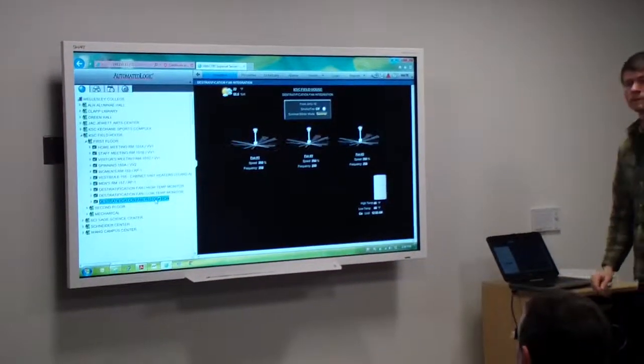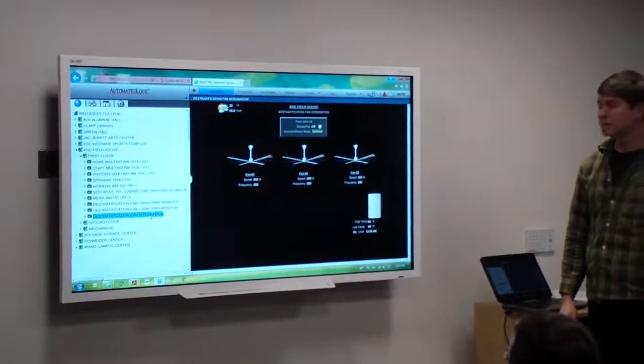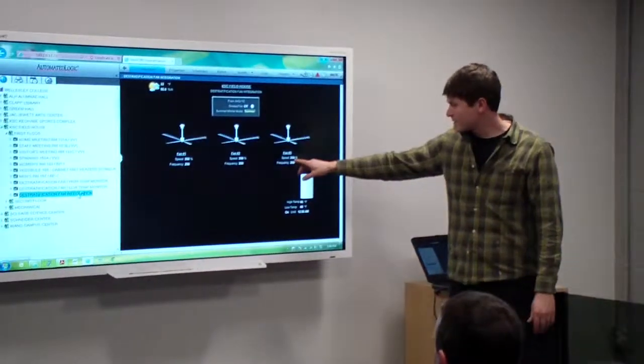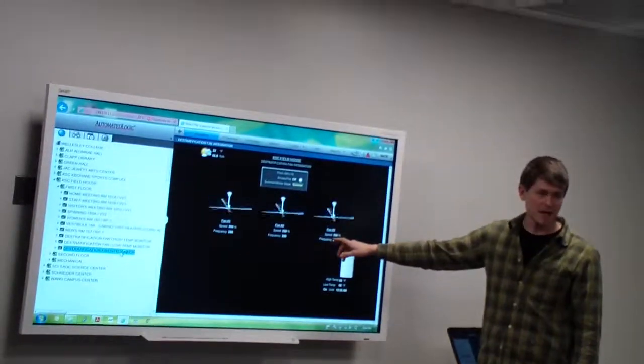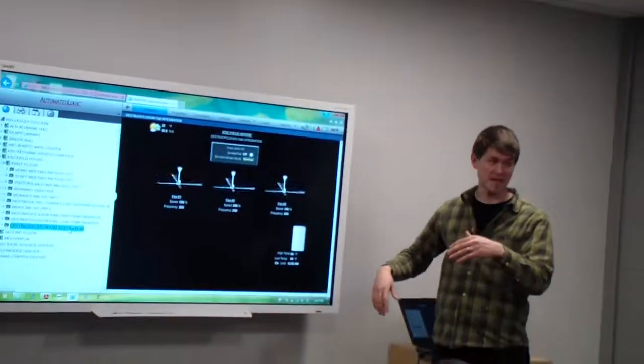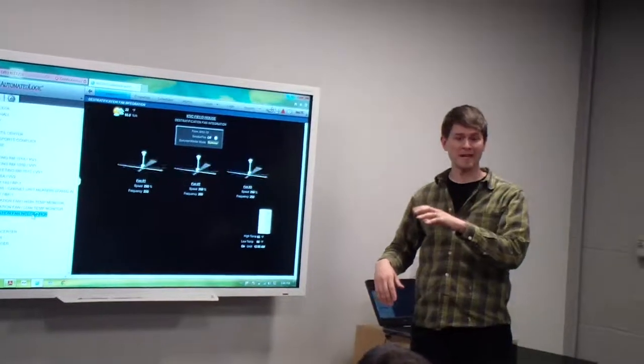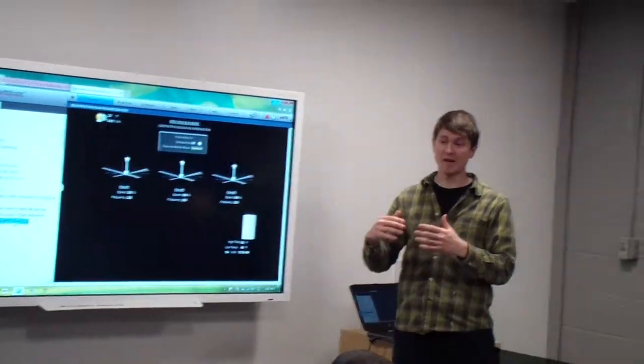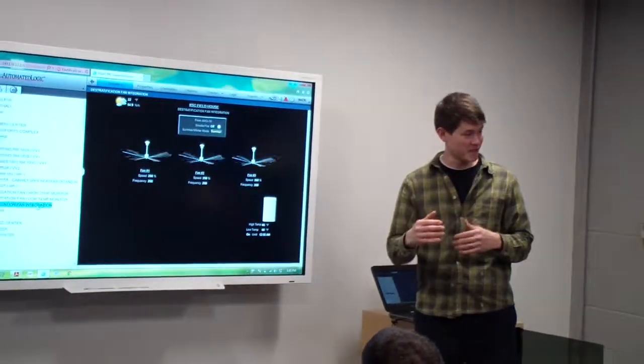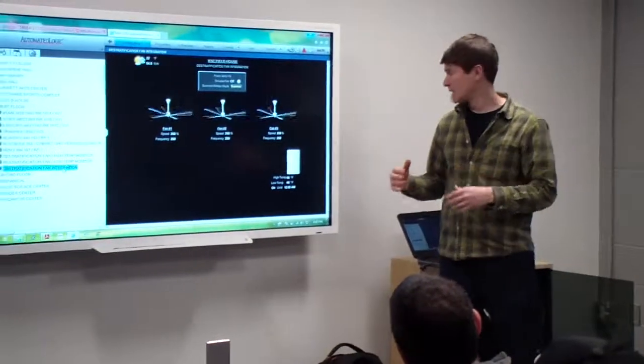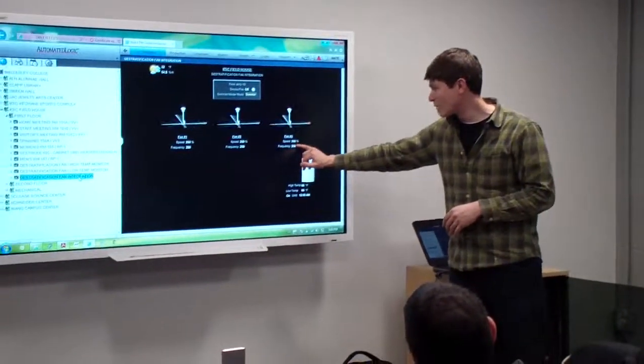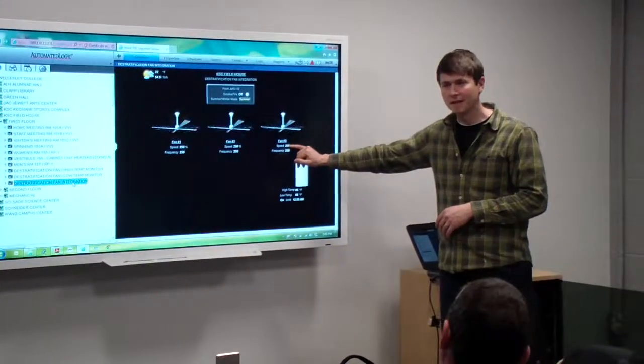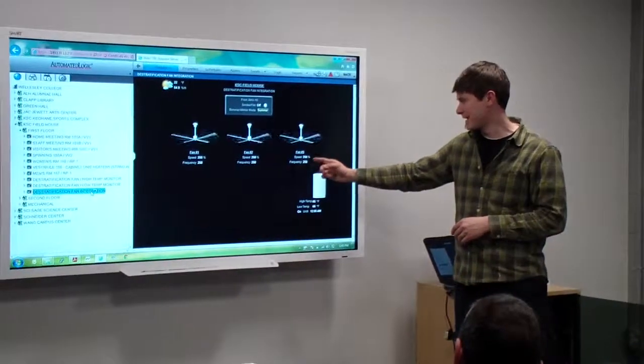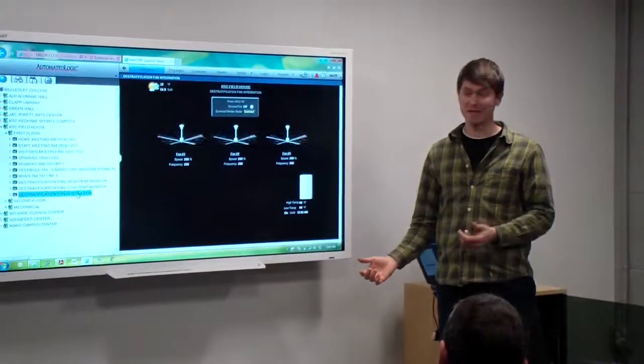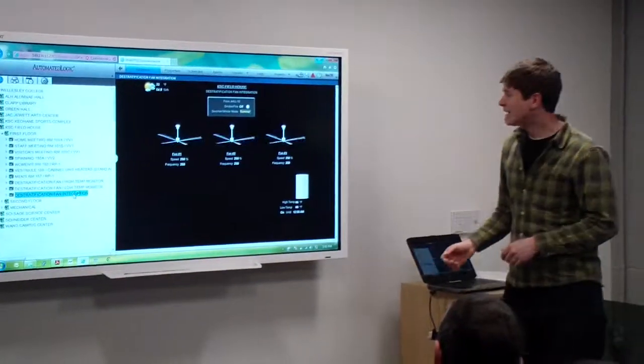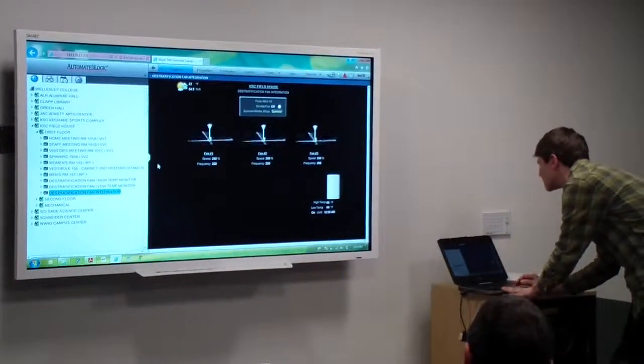Do Dennis and Billy have control of those fans or no? Yes, they do. Through integration, you'll notice that this number seems a little out of whack. The Yaskawa drives look for 100, or a 100 command to them is actually 10%, or 10 hertz to the drive, and a 600 command is 60 hertz to the drive. So I'm going to change the program, we'll do a little division so it'll depict more clearly what's there, because seeing it at 250, it's not spinning at 250% of what the fan's rated for. But yes, they do have full control.